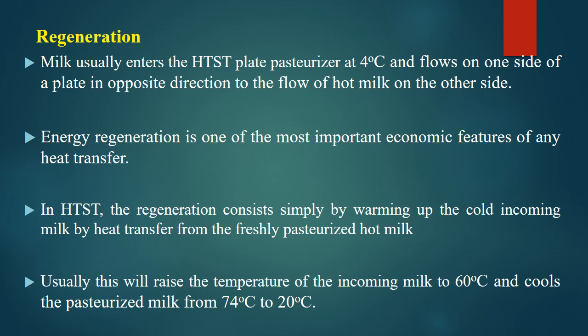Here we have thin plates, so heat exchange will be very good. Between the plates, the thin milk film will move, and the direction of the milk and the heating medium is opposite, so the efficiency of heat transfer will be better. The energy regeneration is one of the most important economic features of any heat transfer. In HTST, regeneration consists simply of warming up the cold incoming milk by heat transfer from the freshly pasteurized hot milk. Usually, this will raise the temperature of the incoming milk to 60 degrees Celsius and cool the pasteurized milk from 74 to 20 degrees Celsius. So here, both ways it is beneficial. Incoming fresh cold milk is getting heated, whereas outgoing hot pasteurized milk, which has to be cooled down, is also getting cooled down. This is the better economic utilization of heat or energy.